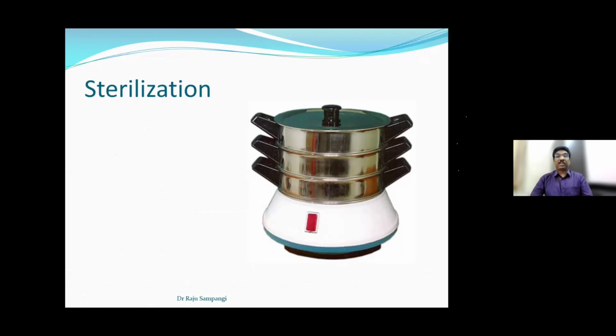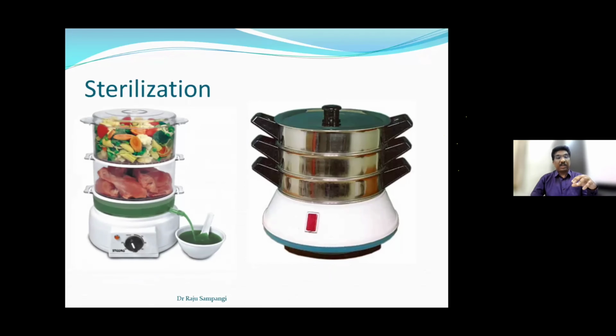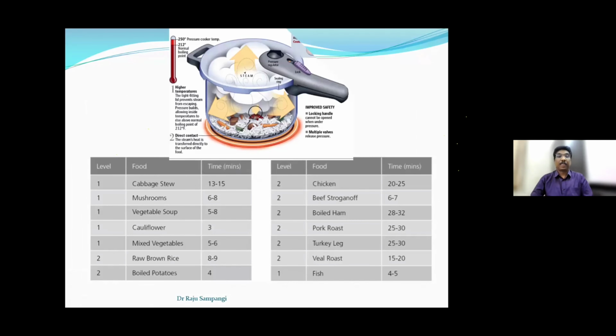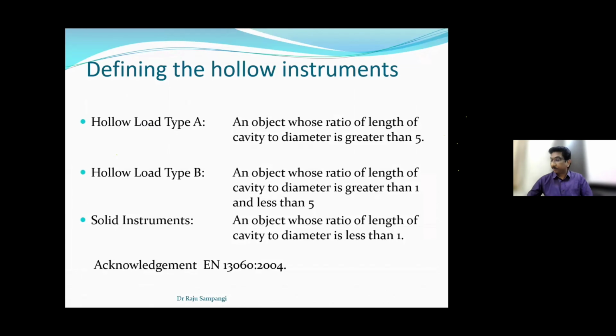Coming back to the sterilization, as I told you, it is similar to cooking. But it's also important to understand what we are cooking inside. Because if I say to cook rice, use a rice cooker for 15 minutes, but inside the rice cooker you're also putting meat, then you need to use a different time and duration. So you cannot use the same time and duration for that.